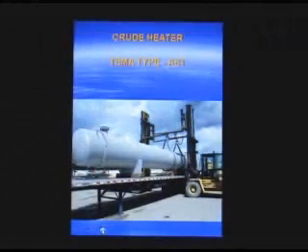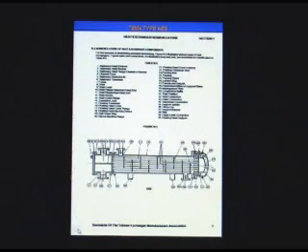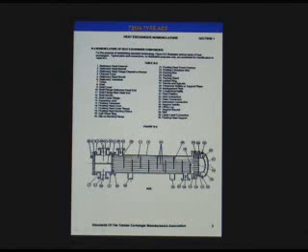This is an example of an AET type floating head. The only difference between that and the one that we saw is that this is now a full diameter floating head, and you would have the ability on a T-type head to actually pull the bundle. The shell diameter would be equal to the head cover diameter that's here. So if you wanted to, you could unbolt these flanges and extract the bundle from the shell, all in the channel side. So you would pull it out in that direction.